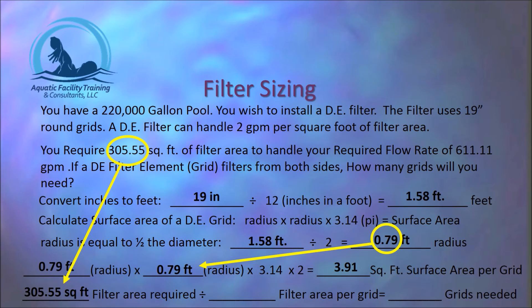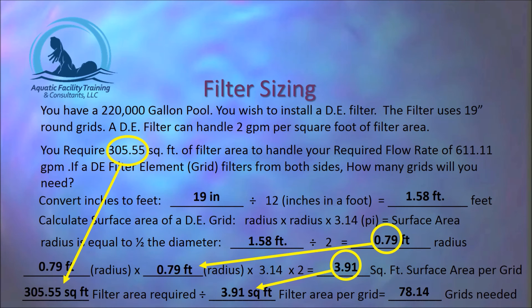Taking the total filter area required — 305.55 square feet — and dividing by 3.91 square feet per grid, we get 78.14 grids, which we round up to 79. We require a quantity of 79 nineteen-inch grids in order to turn over 220,000 gallons in 6 hours at a flow rate of 611.11 gallons per minute.